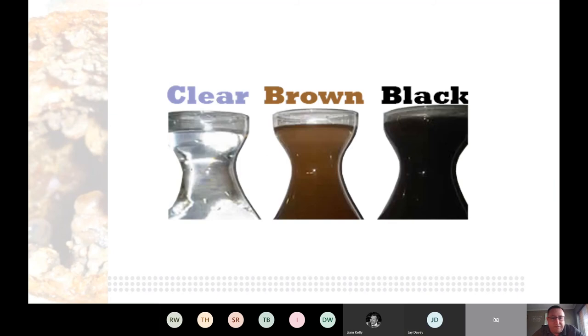I'd normally have two bottles of water — one brown, one black. Both plumbers I asked picked black as the worst, but actually it's the brown, because that shows active oxygen in the system. Active oxygen is one of the things that will kill a system quicker than anything else. The black water is magnetite — iron oxide — which shows there's no active oxygen present.